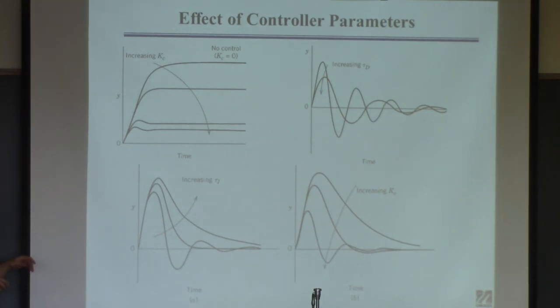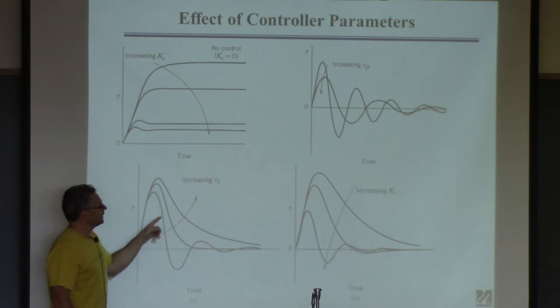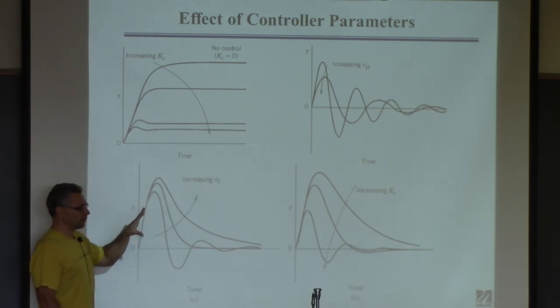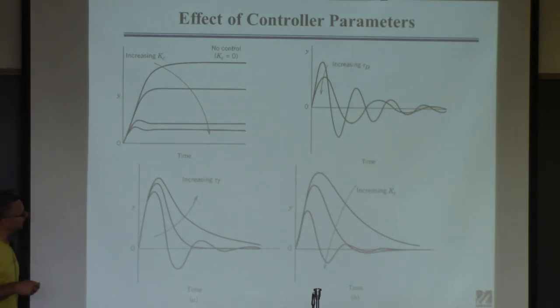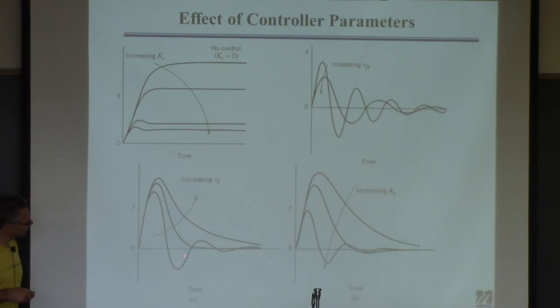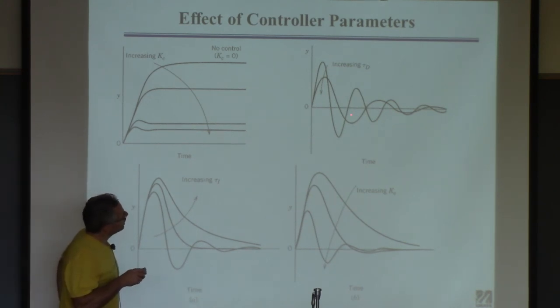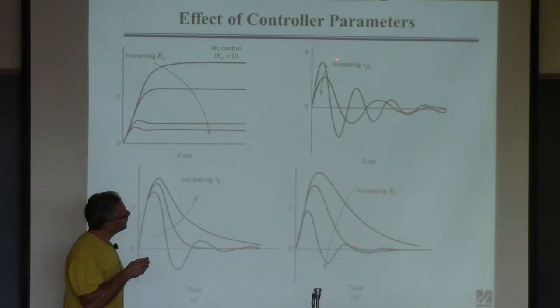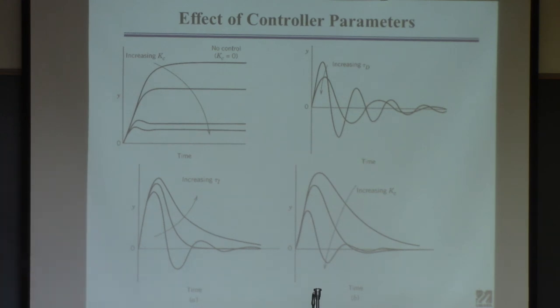For the derivative term: increasing τD can damp out oscillations and make the controller more stable — the bigger the derivative term, the more stable the controller. That's true, provided the signal is clean and not noisy.